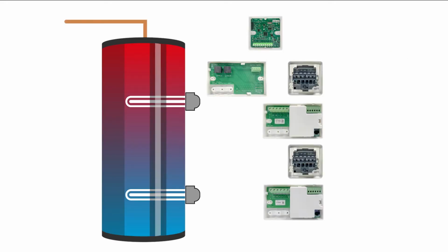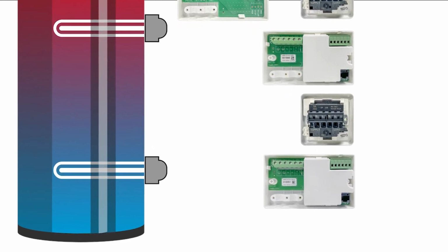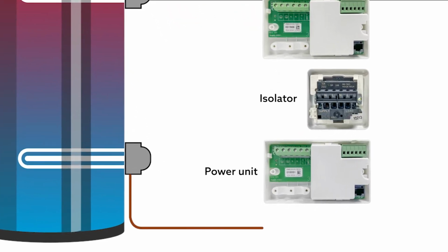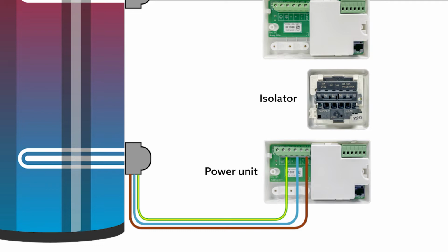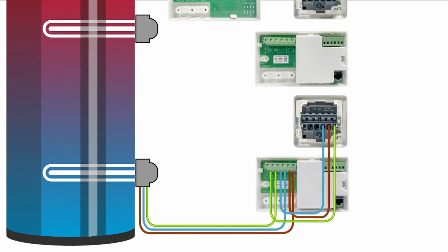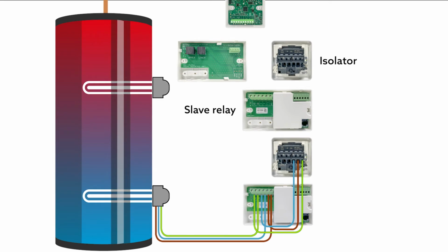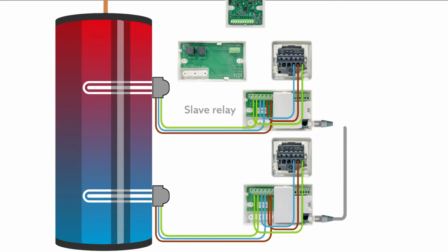Wiring the elements. The live wire from the bottom element connects to the power unit's load terminal. The neutral and earth wires connect to their respective load terminals. Use 3-core cable to connect the power unit to the appropriate isolator, taking the isolator load live to the live on the power unit, and the neutral and earth wires from the isolator load to the neutral and earth terminals on the power unit. Use the same process to connect the top element to the slave relay and its isolator. Connect the power unit to the slave relay using the short RJ45.